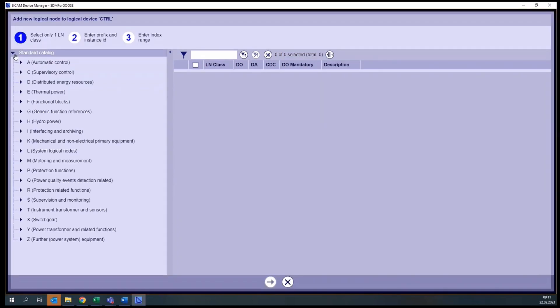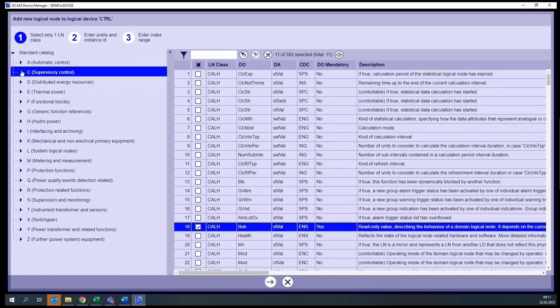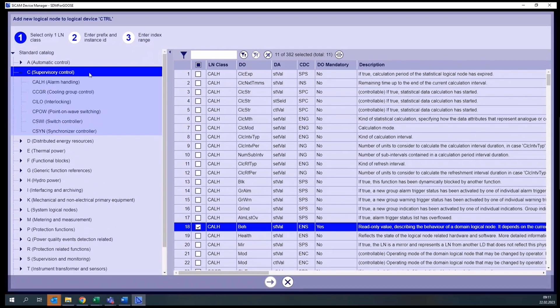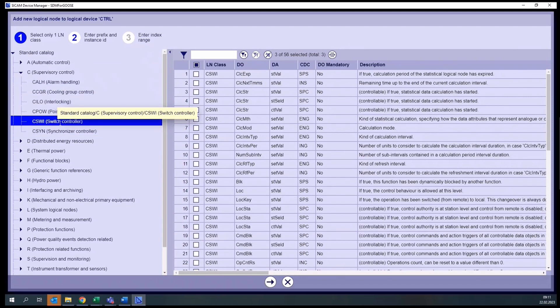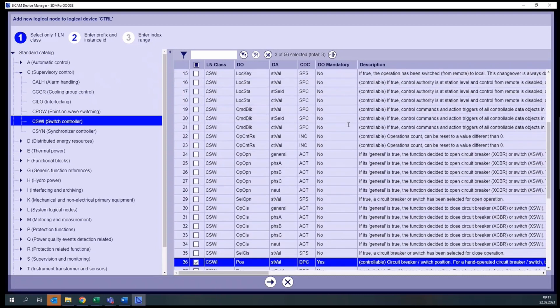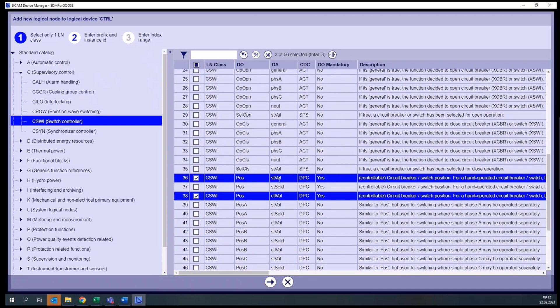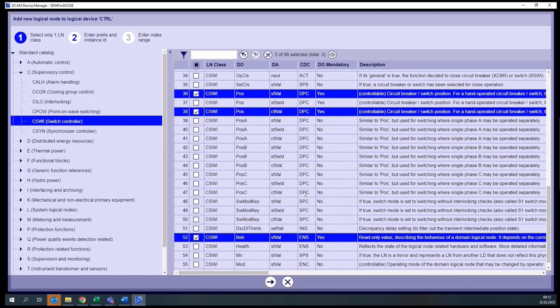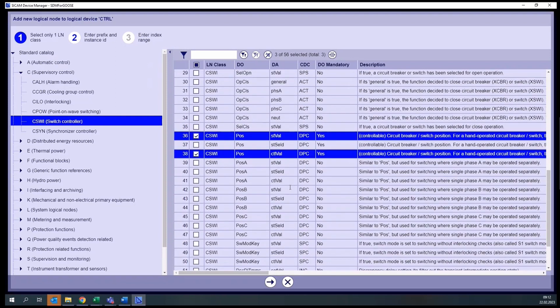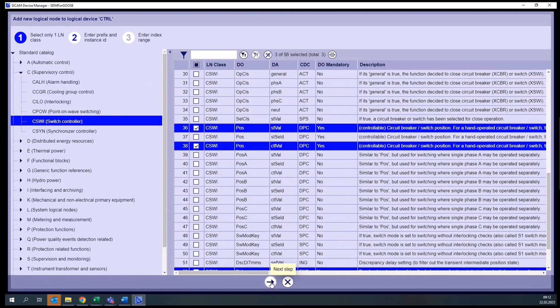In this example, let's assume we want to create four different switching devices. According to IEC 61850, they can be found under C, Supervisory Control, and then we go to the logical nodes for switch controller. Now you see all elements available for this type of logical node. While some of them are mandatory in the data model, some are not. You can select which ones should be available. It is important to have the position and the command. We will not use the Beh element, but since it is mandatory we will just leave it in the data model, although we will not create a signal for it.